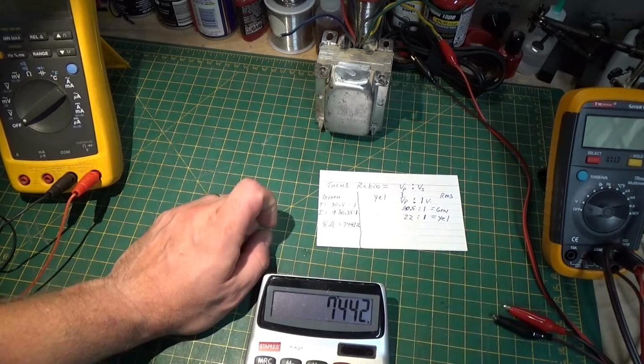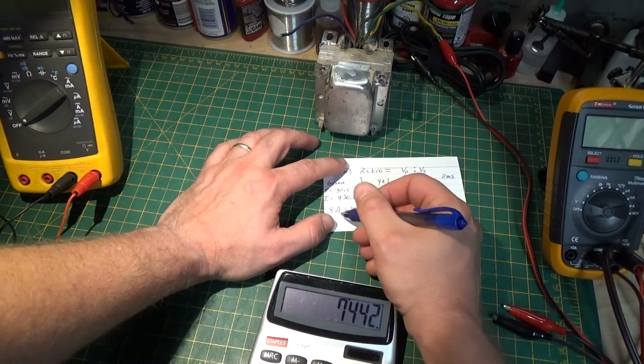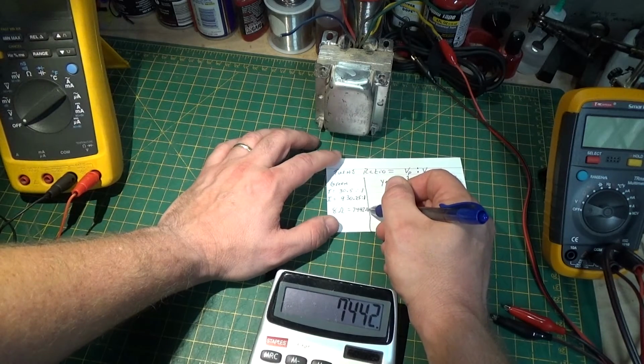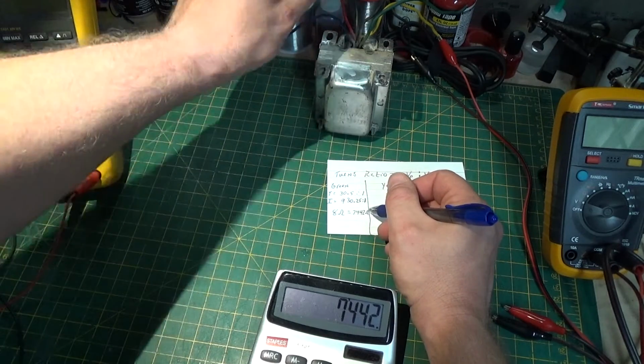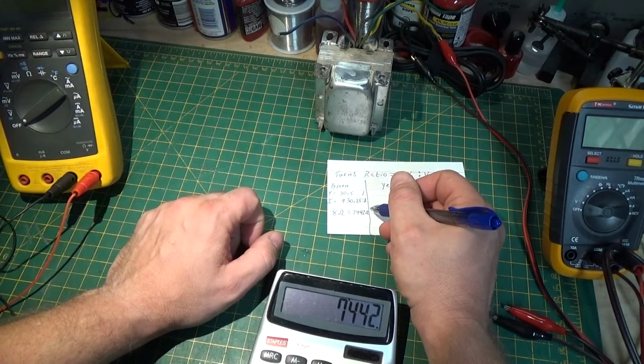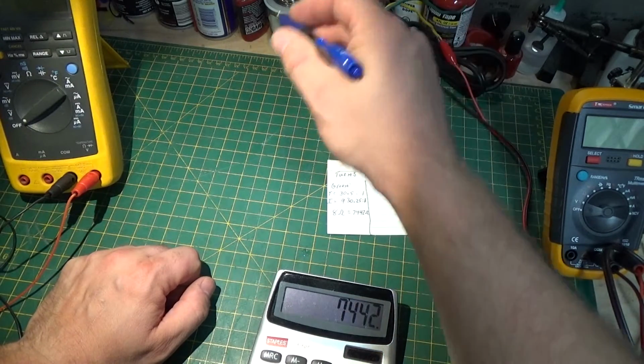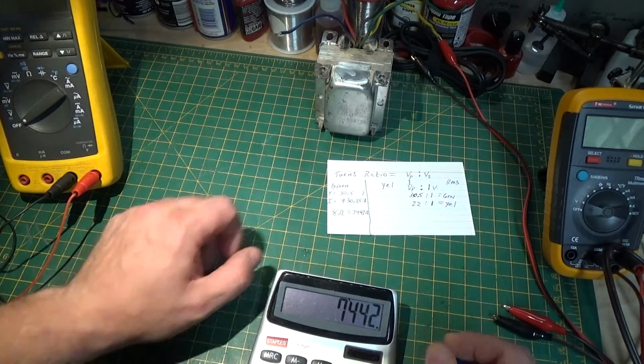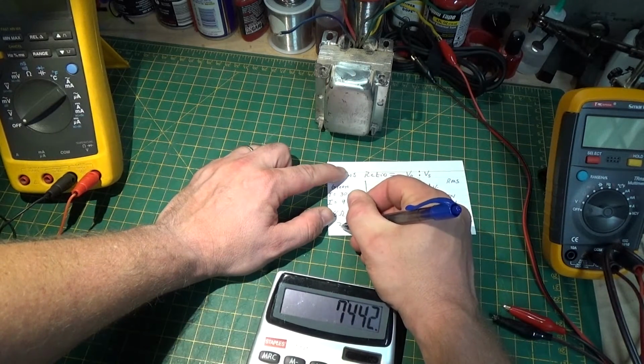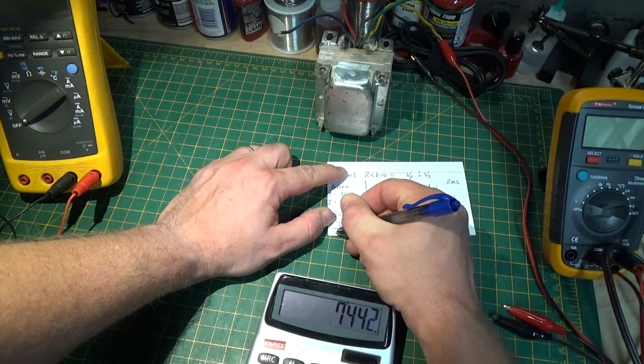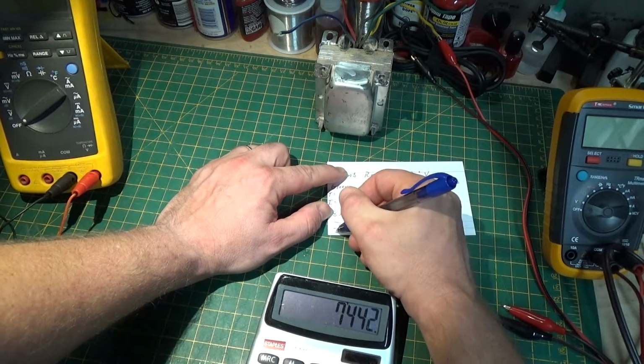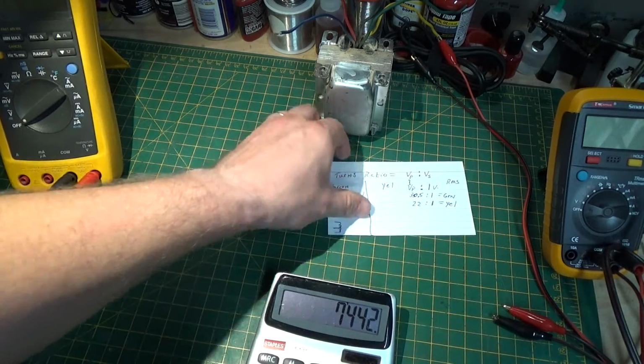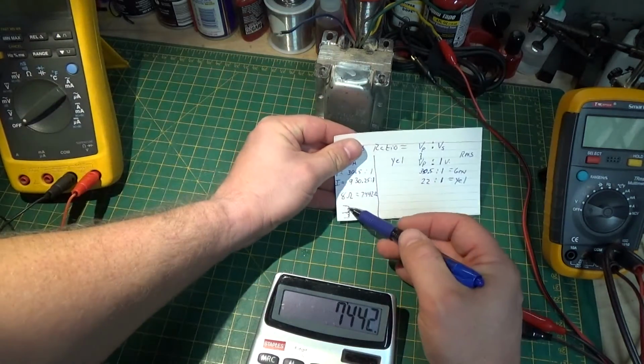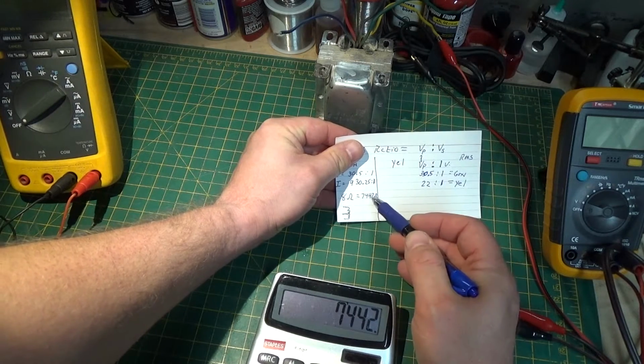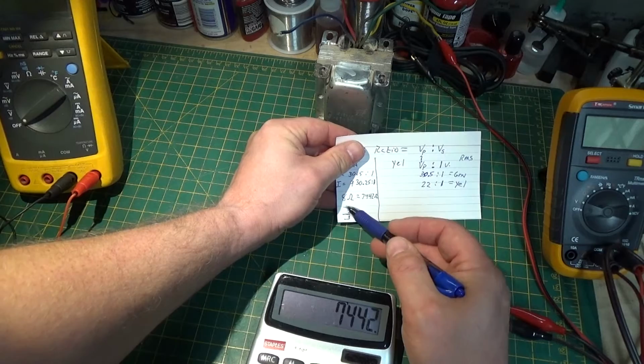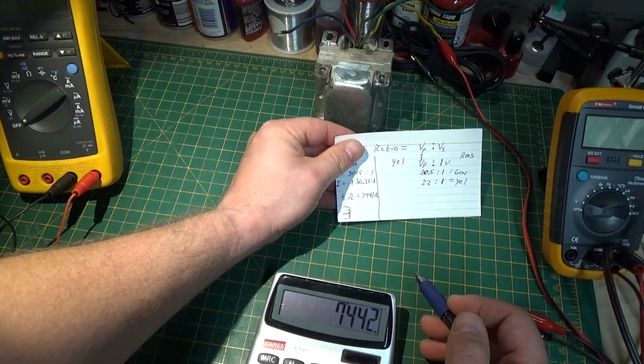So that's where we test it at. So basically, this would be a 7.4K load if we use this as a single-ended transformer, with respect to the two outside leads. In other words, your primary looks like this: you've got the two blue leads here and the red lead here, see that?